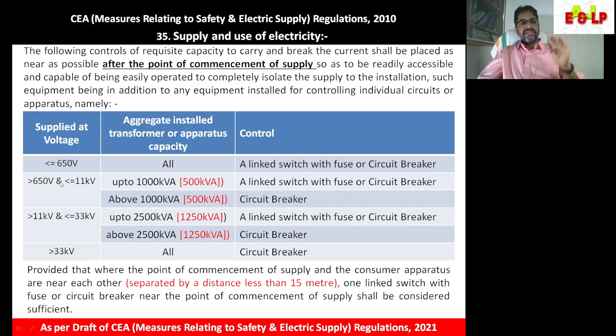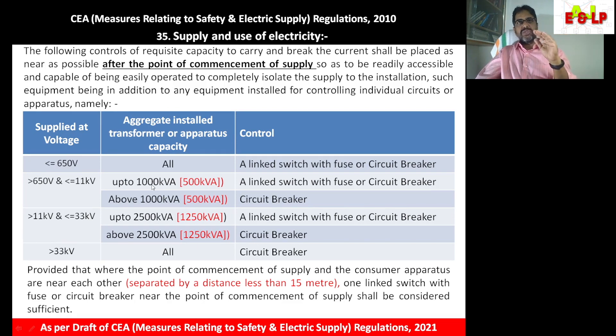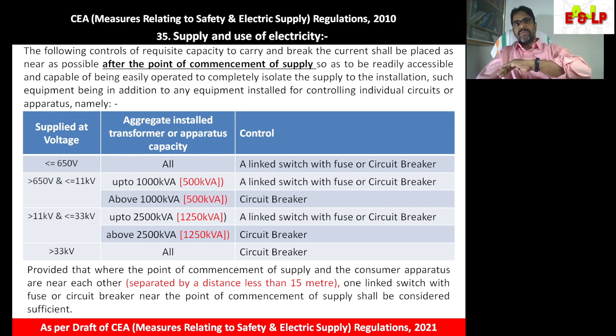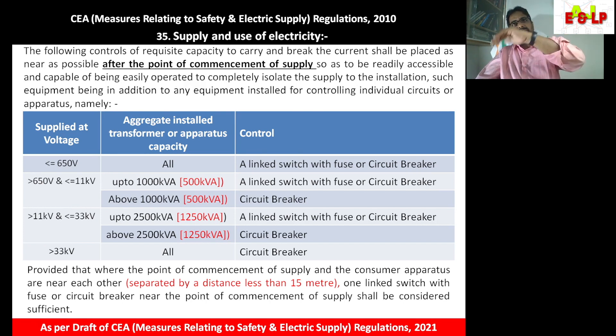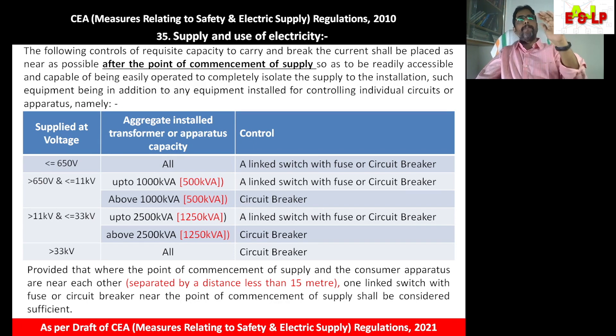The next category is where consumer voltage is between 650V and 11kV — meaning an HT consumer. If such a consumer has a transformer rating up to 1000 KVA, there must be a linked switch-fuse unit or a circuit breaker. We can provide either an HT switch-fuse unit or a circuit breaker such as a VCB. Above 1000 KVA, a circuit breaker is compulsory.